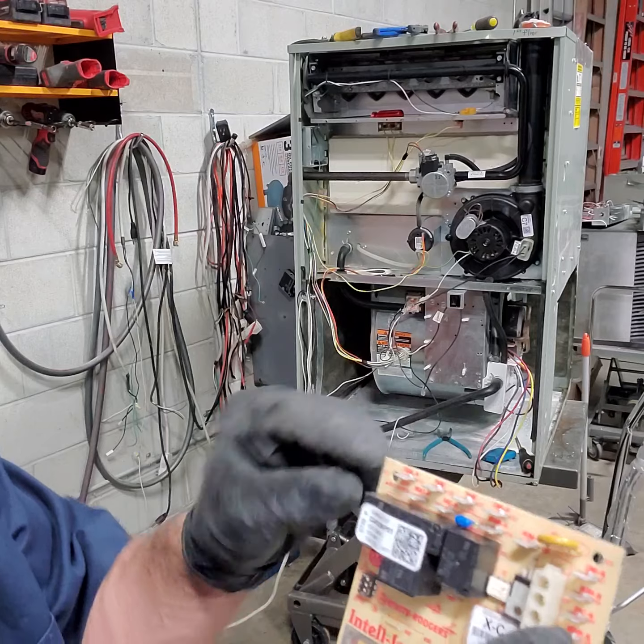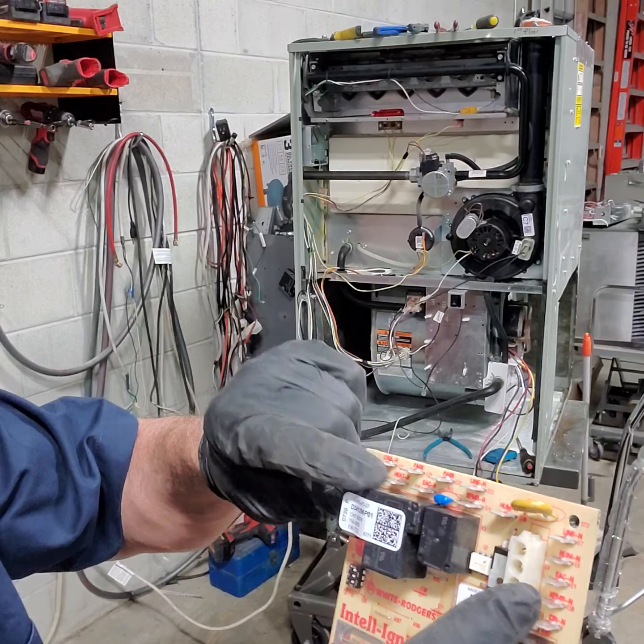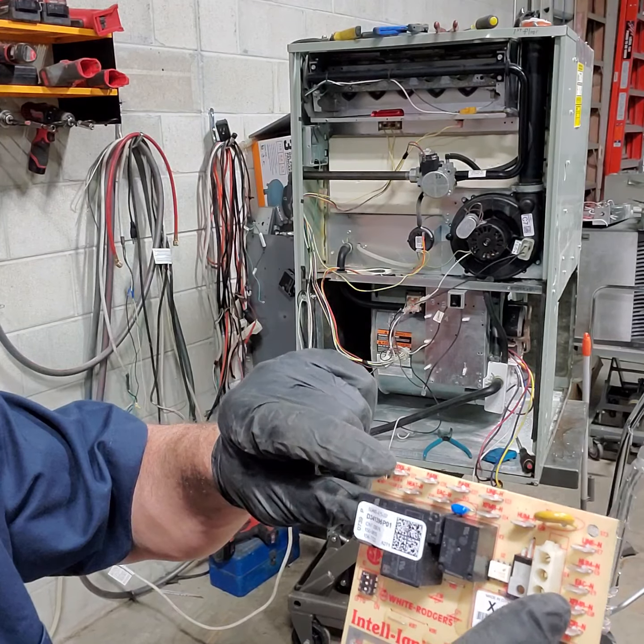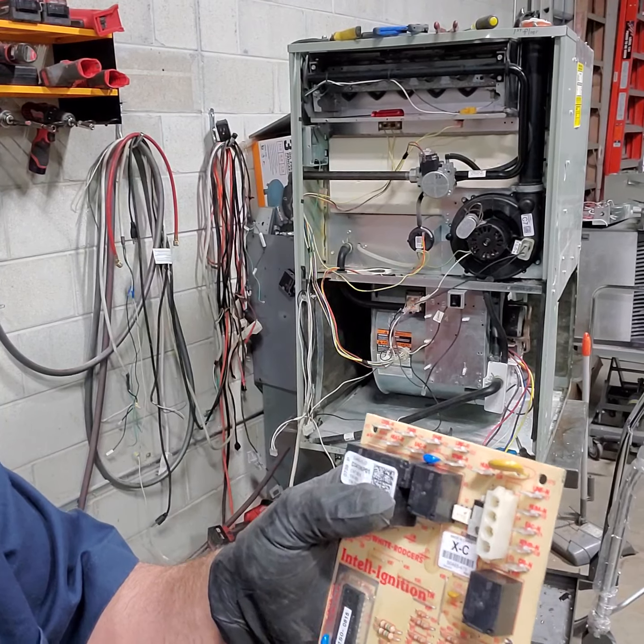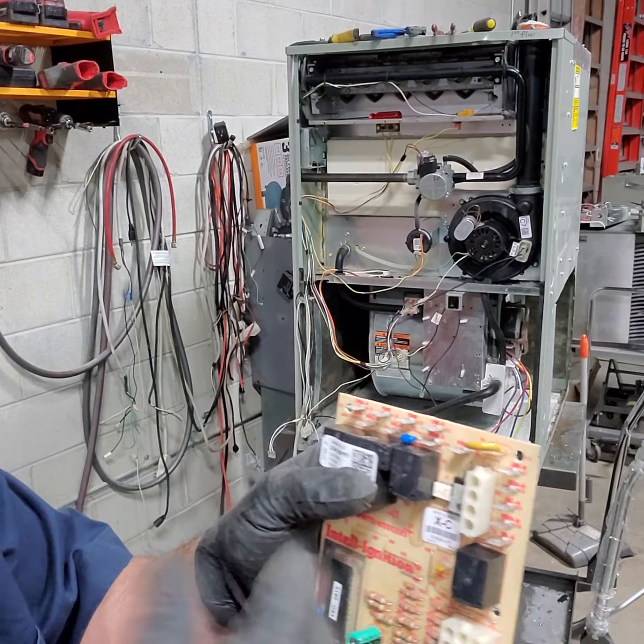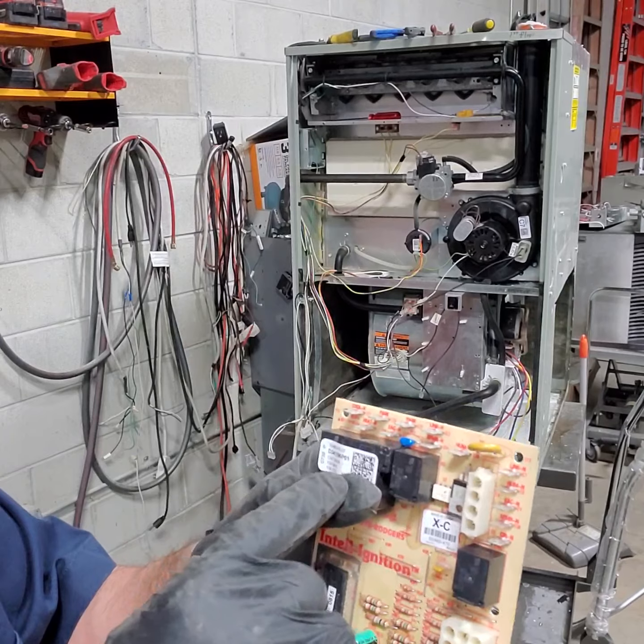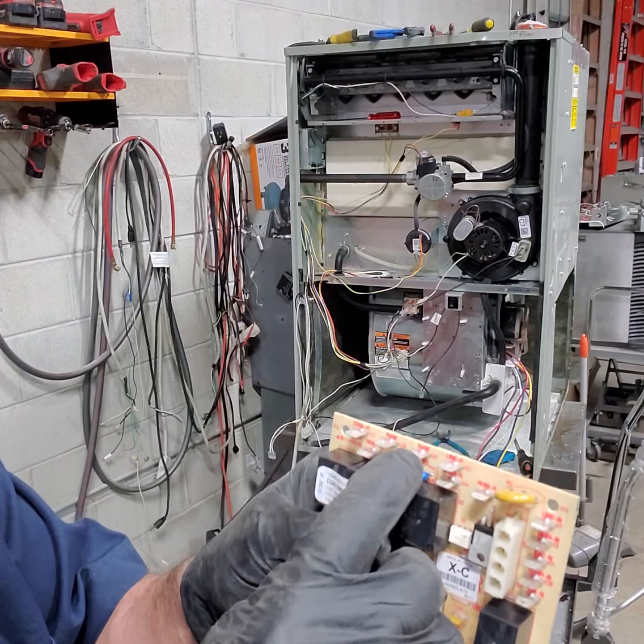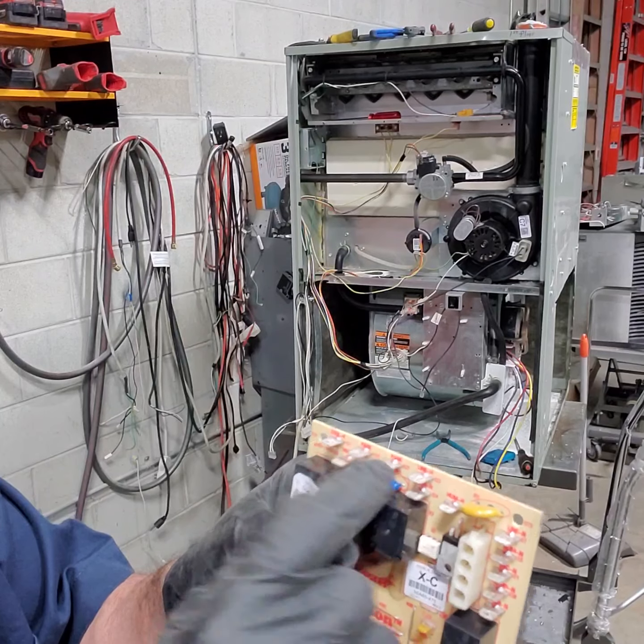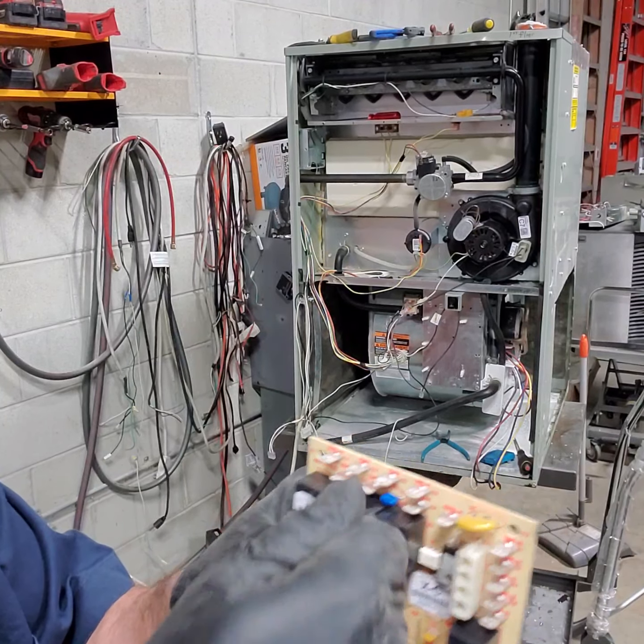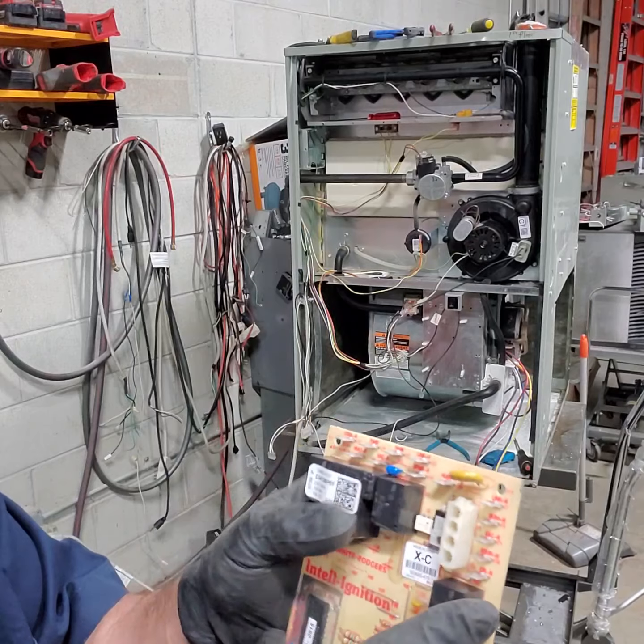Let's say you use only two-speed: red and black, low and high. Then you have the other two-speed wires, what do you do with them? You don't leave them laying around the furnace since they might short or hit the chassis. So I put them on park, which is a dead, dummy connection, but safe. When you put them here, the wire doesn't move anymore.